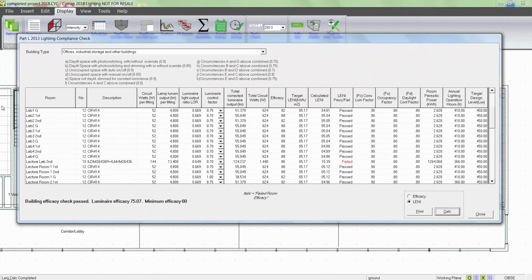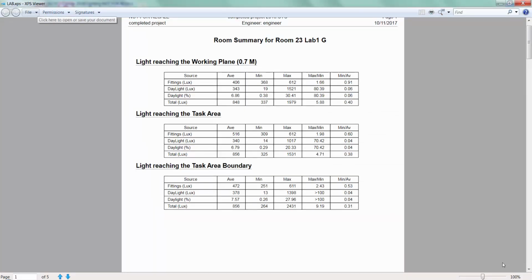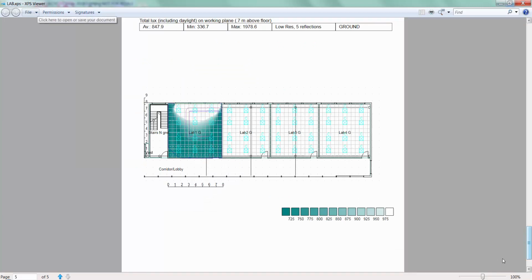For sustainability reasons, compliance is key, so the software enables you to undertake a Part L test, a full lighting energy numeric indicator test, and also the LG7 compliancy in terms of contrast between working plane and wall can be considered. Input data plus calculation data can be fully reported, as can screen plots. There's a full suite of reports on either individual spaces or as a summary.